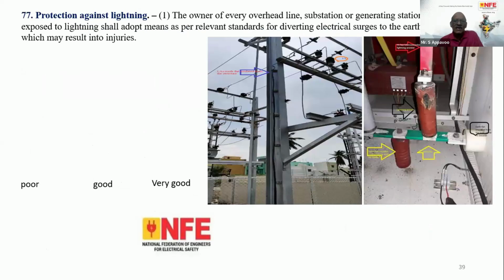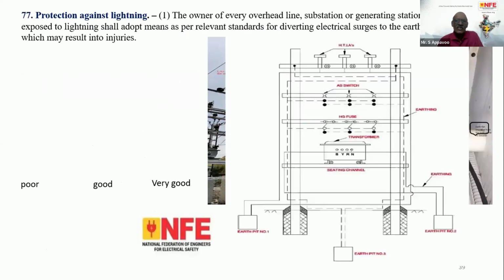So this is the concept, just one slide. This is the concept that we regularly adopt. We provide the lightning arrester at the top. So as a result, this equipment, the transformer, is somewhere here. This is at the top. The distance in the loop formed by the down conductor and the equipment to be protected is very high. As a result, during the discharge of lightning, your lightning arrester becomes the victim. It doesn't protect. Instead of protecting the transformers from BIL, basic insulation level, your lightning arrester is becoming a victim.